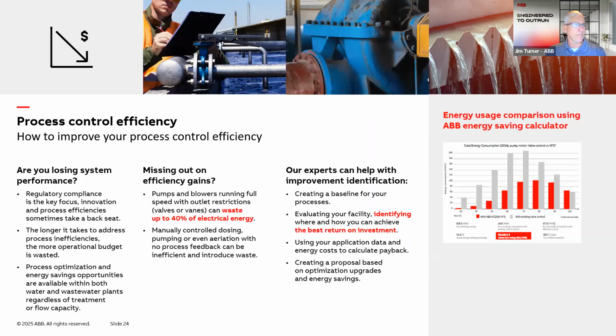We show a little picture of it there on the side that allows you to compare the energy spent on a throttling valve compared to a variable frequency drive application and estimate the savings over time. So the needed system parameters are horsepower of the pump, the load or runtime hours of the system, and the cost of energy. With those three elements, we can actually calculate the savings based on that load profile. And you can contact some of our water specialists to assist you both in validating the application as a good fit for variable frequency drives and making these comparisons.